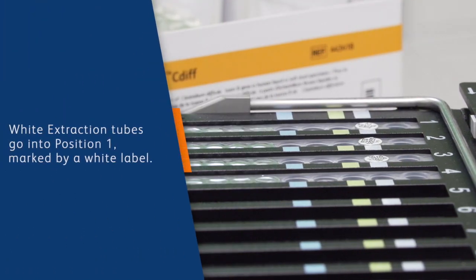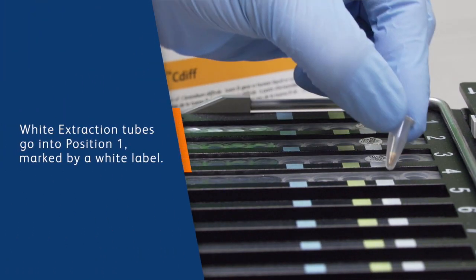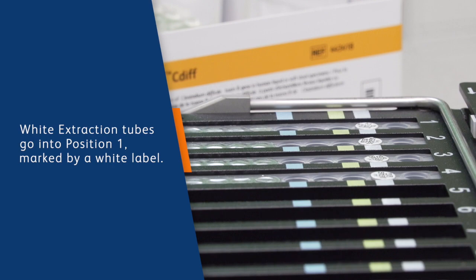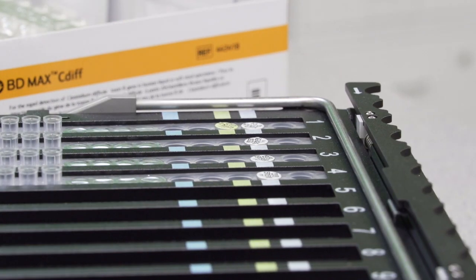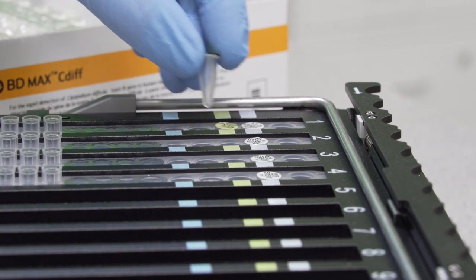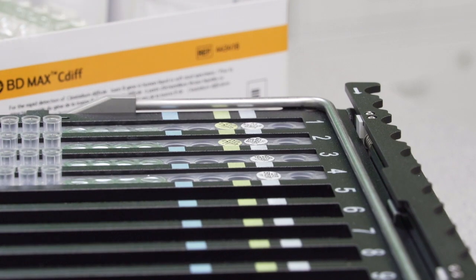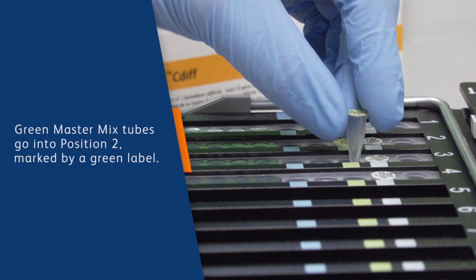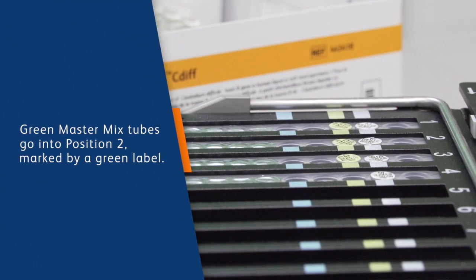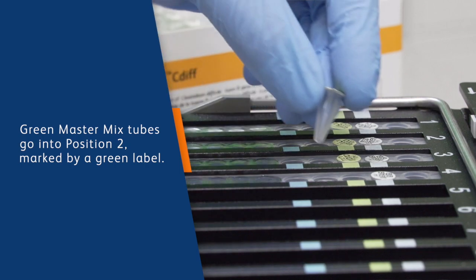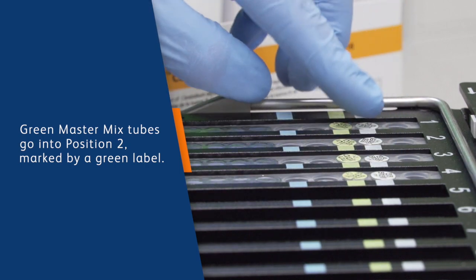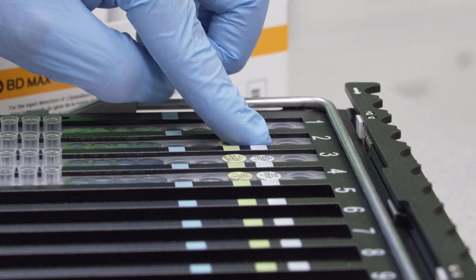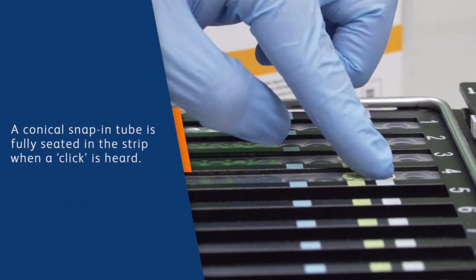Snap one extraction tube into each unitized reagent strip in position 1, which is marked by a white label. Then, take the master mix out, which has a green foil label and has all the enzymes and probes. Snap one master mix tube into each unitized reagent strip in position 2, which is marked by the green label. You can see that the colored stripes on the rack line up with the colors on the snap-ins.